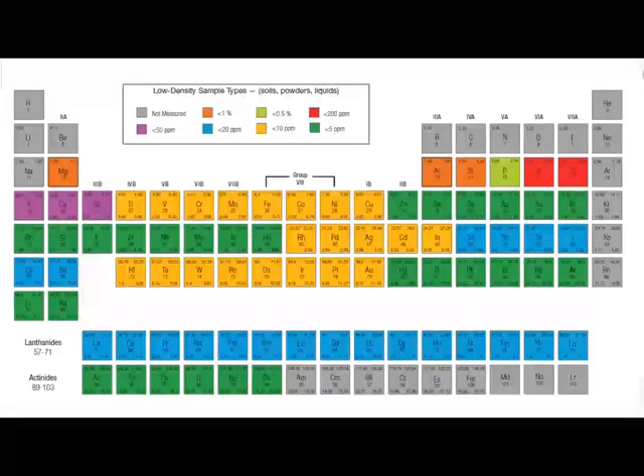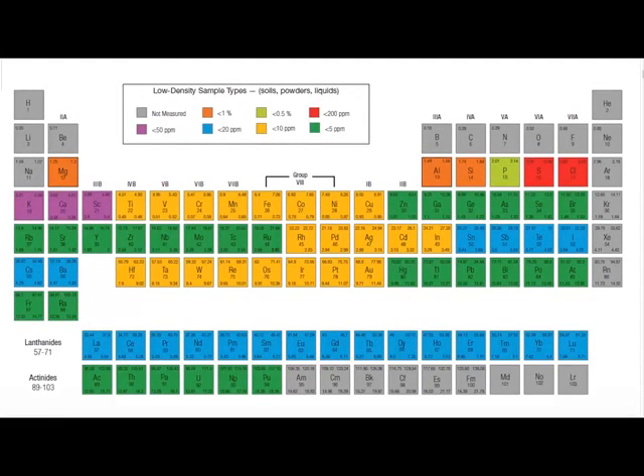Please keep in mind this is X-ray tube type technology. It's completely electrical and does not utilize radioisotopes. Let's talk about the periodic table. What elements can you detect with handheld XRF? Currently, handheld XRF has an effective range from magnesium to uranium on the periodic table. Magnesium would be the lightest element that can be effectively quantified. It's almost all elements of significant value in the scrap industry, including precious metals. Elements lighter than magnesium, such as carbon and boron, are most difficult to analyze.